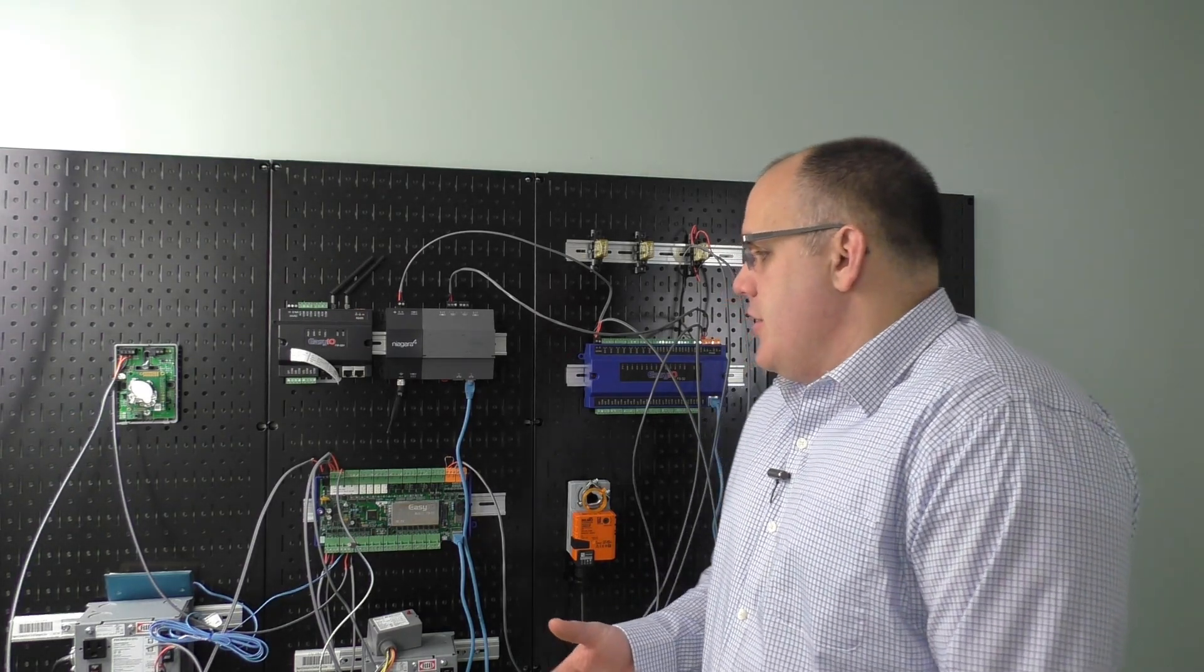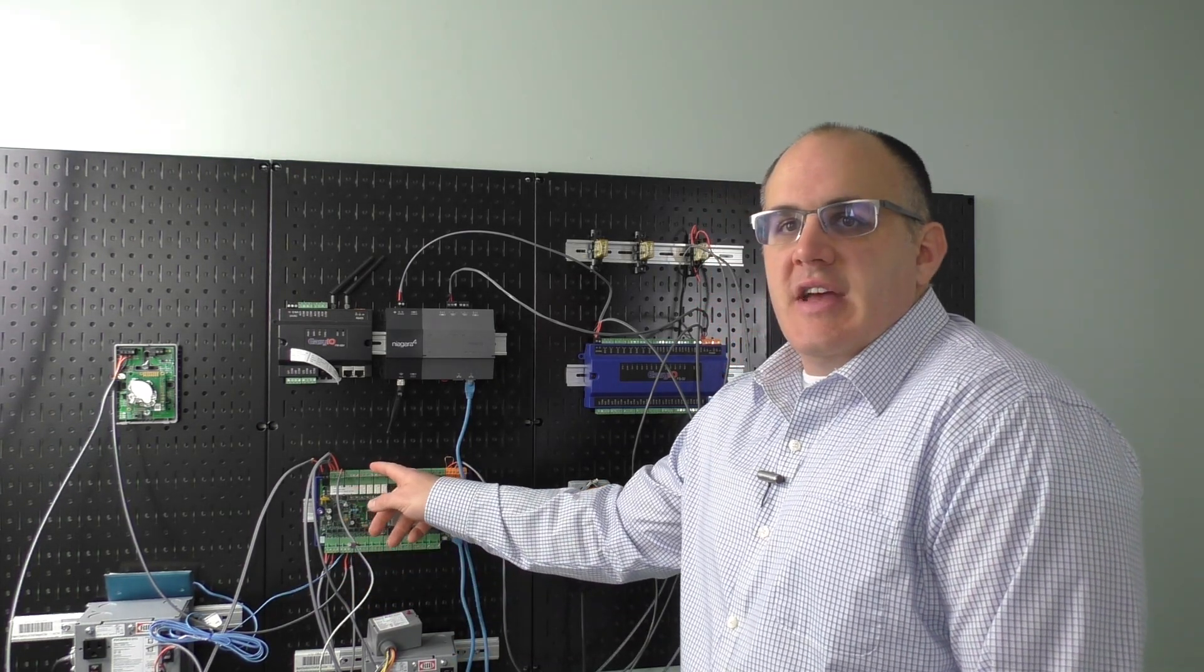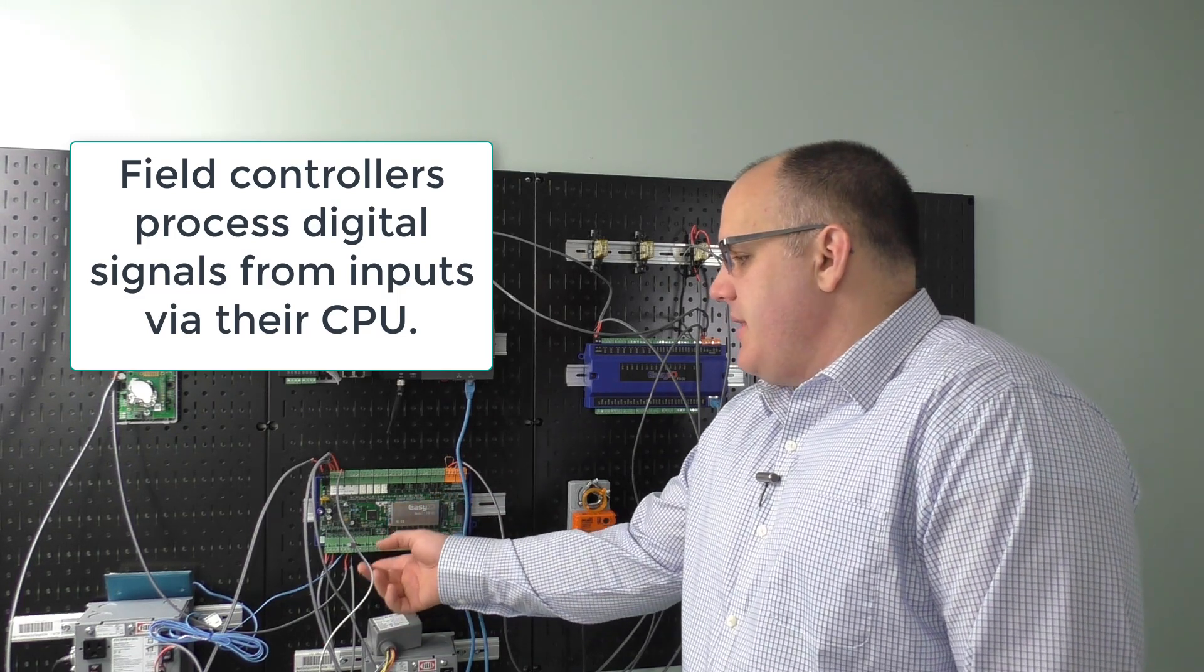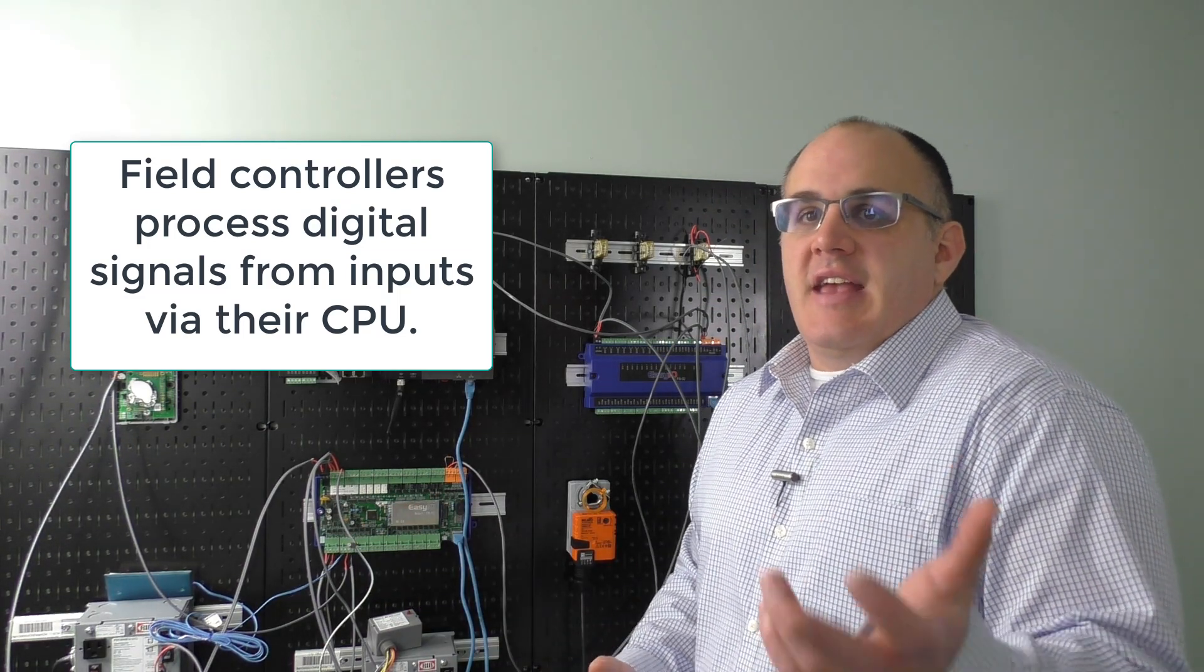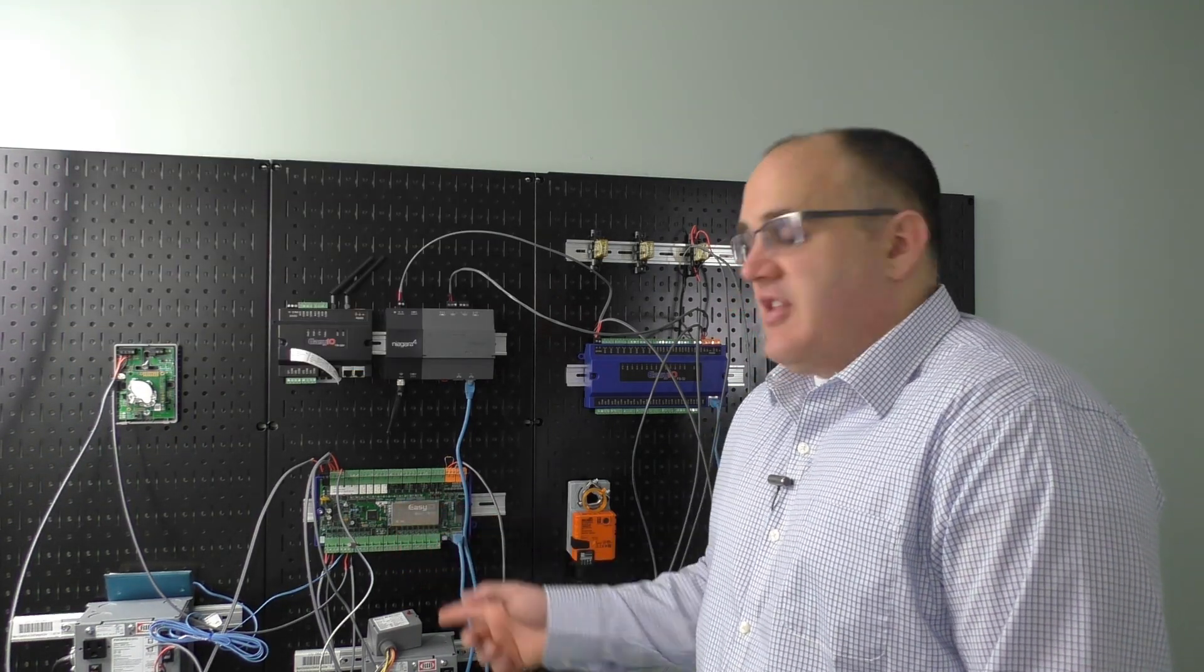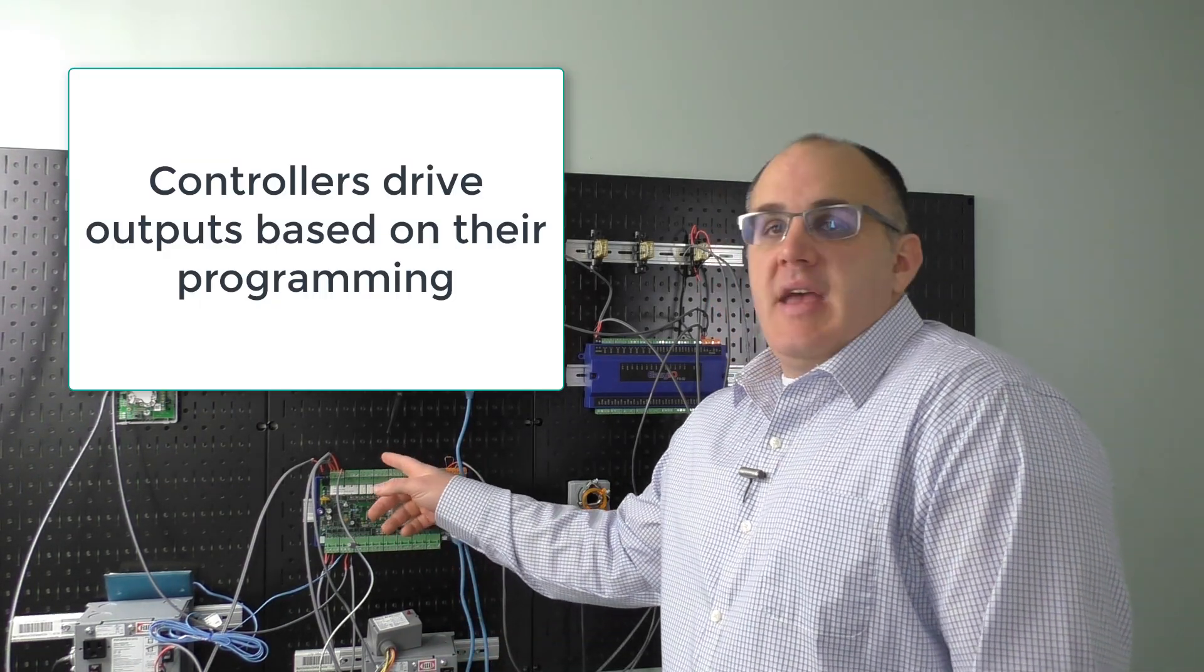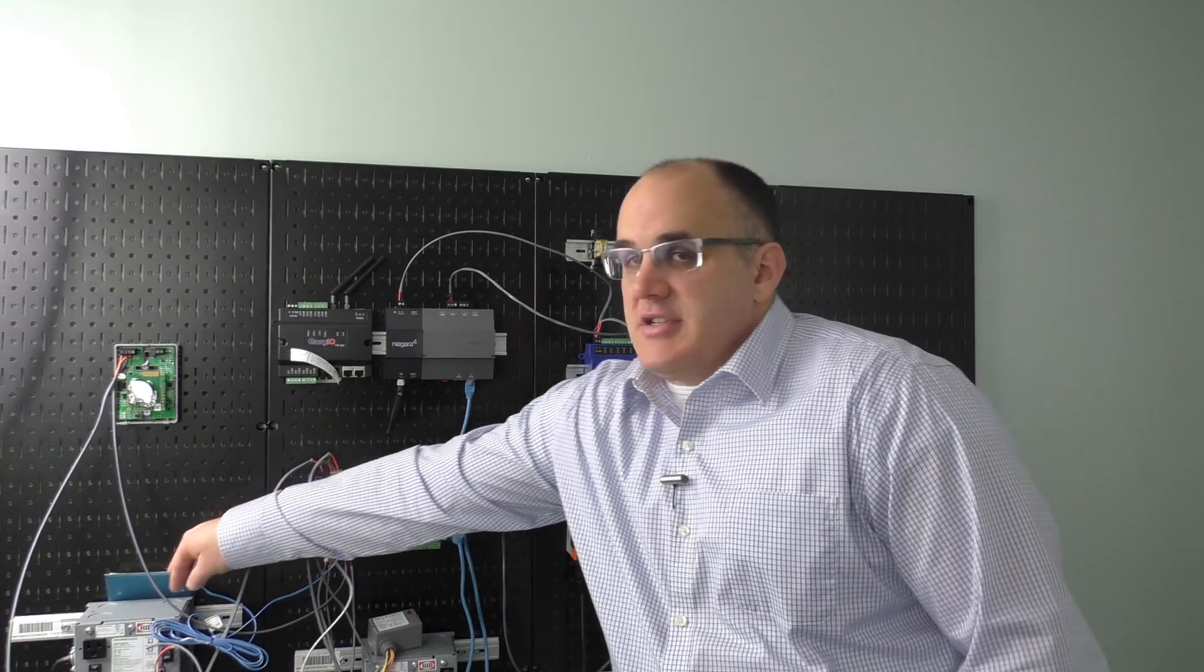So what are inputs and outputs? We've got a field controller here, and we have inputs coming into the field controller and outputs coming out. Inputs come into this field controller and get processed and turned into digital signals, hence why we have DDC controllers, direct digital controllers. They take any form of input and convert it to a digital signal that can be processed by the CPU in the controller. This CPU then makes decisions that may or may not drive outputs. Now, let's take a greater look at some inputs, but let's first talk about different input types.